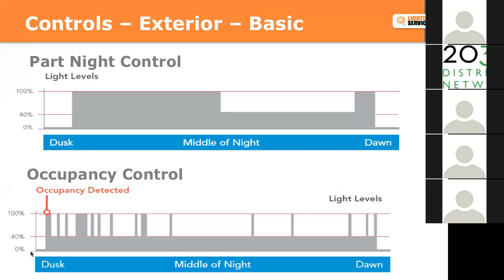Occupancy control is similar to putting an occupancy sensor on an exterior fixture. Most of the time they're built into the unit itself, operating very similar to an interior occupancy control, which may scare some of you given the history of occupancy sensors and people waving their hands to make them work. We've had very good success with these, and they save a lot of energy as well as act as a deterrent for vandalism or trespassing, since lights initially come on at 100% brightness, dim down to a preset level, and ramp back up as motion is detected.